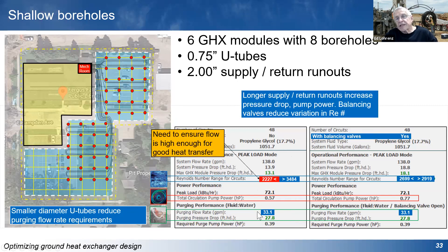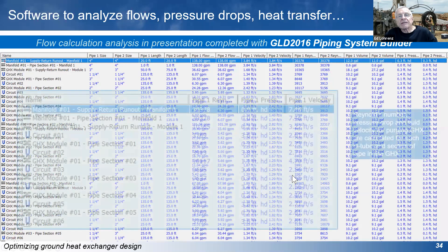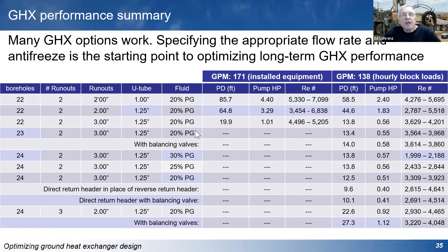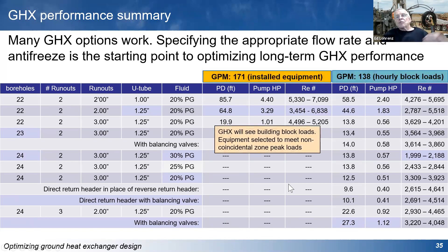That reduces the flow rate needed to flush air down to about 33 GPM per module when flushing individually. There is software available that gives you a detailed look at flow rate through each circuit, pressure drop, pipe velocity during purging, and verifies you're above two feet per second with reasonably equal pressure drops and adequate Reynolds numbers. Basically, there are a lot of different ways to design the ground heat exchanger — it's going to have an impact on pump size and the flow rate at which the system is designed to operate. Using block loads rather than design loads will give you better performance while still meeting the heating and cooling needs of the building.